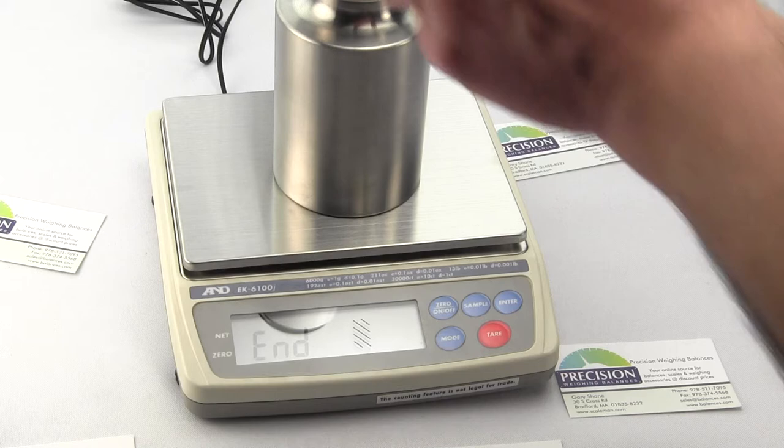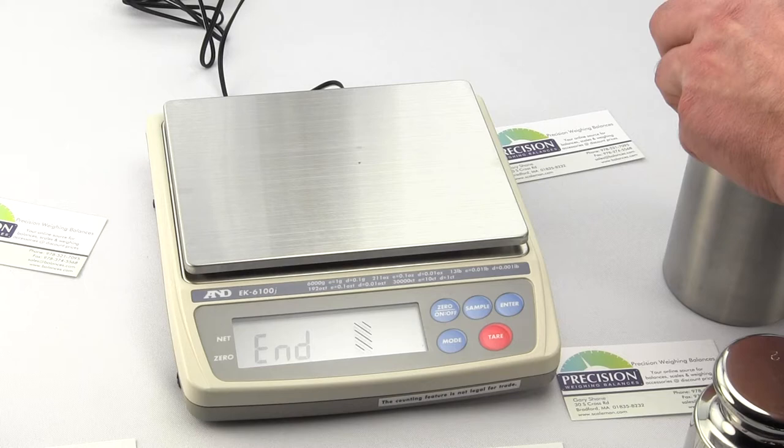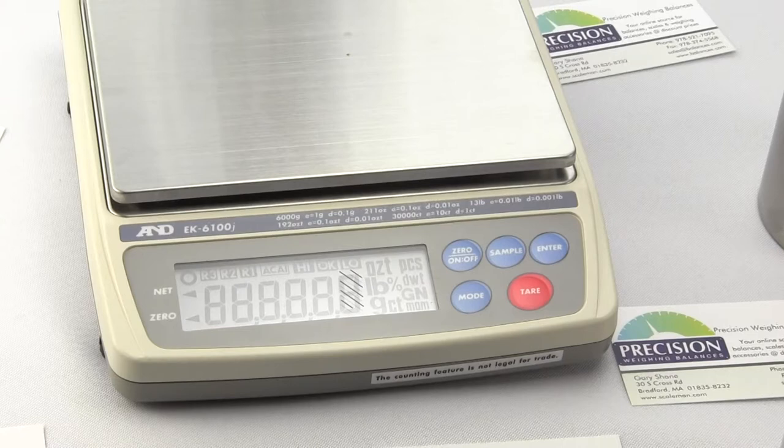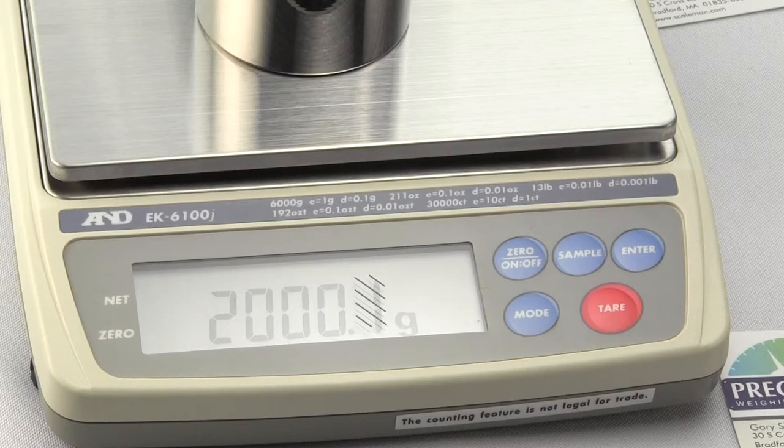Remove the weights. Press the MODE button. Returns the scale back to the weighing mode. Simply put a weight on. And your scale is calibrated.